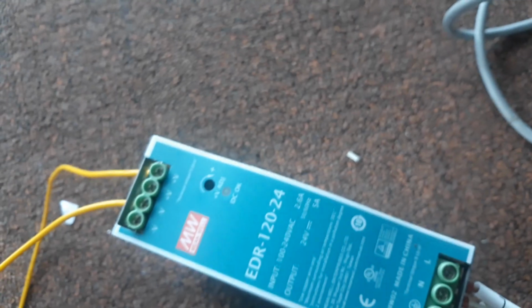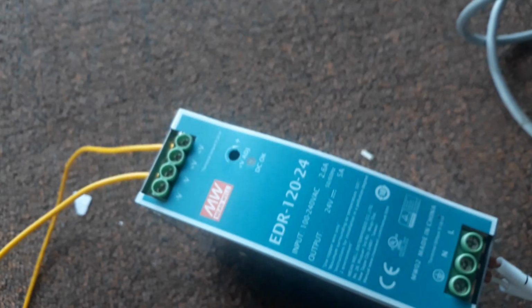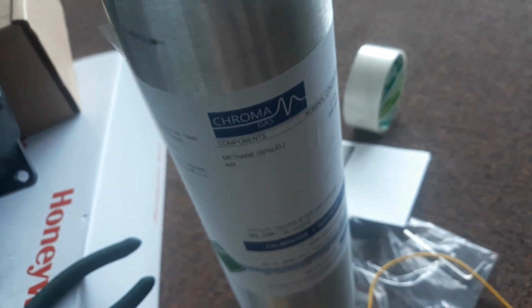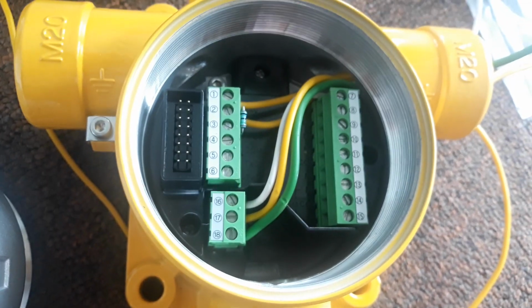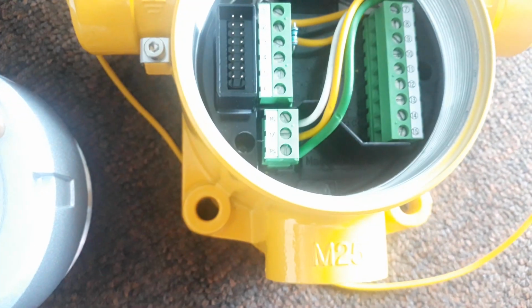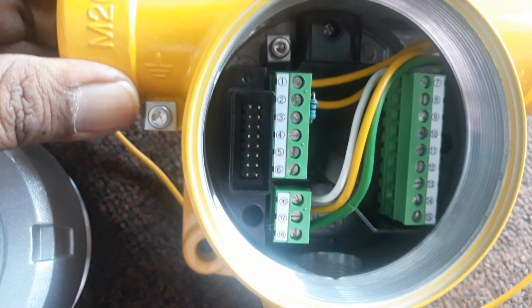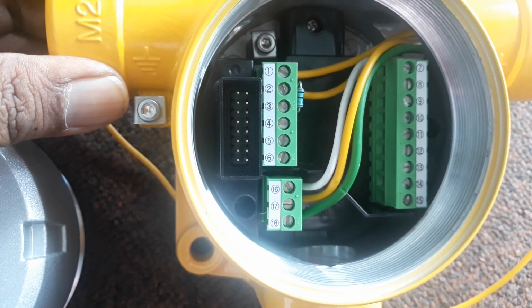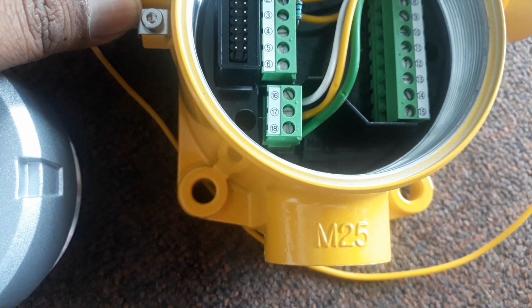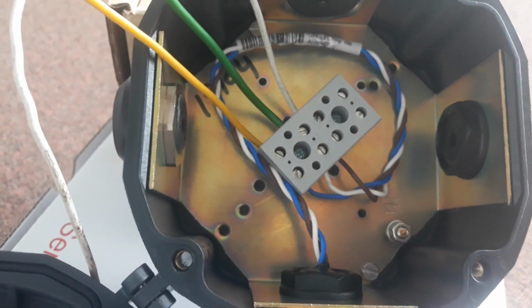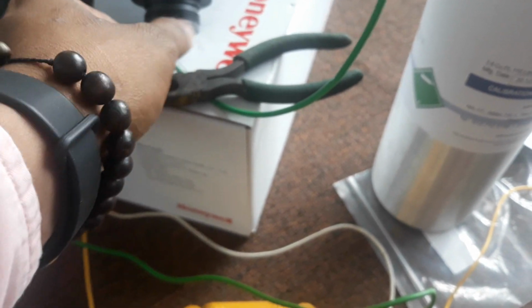How to start up? You must have a power supply. I got the power supply from Honeywell, 24 VDC. And I also have a calibration gas for 50% LEL. Okay, first you must do the 24 volt power cable. Positive is terminal 1 and negative is terminal 2. Terminals 16, 17 and 18 you connect here. For this you must read the instruction manual. Okay, I have a hose for doing the gas detection.